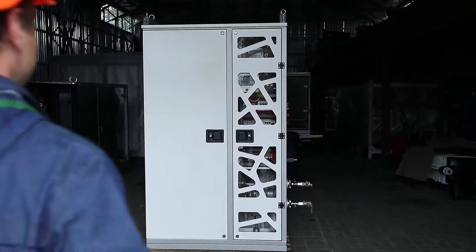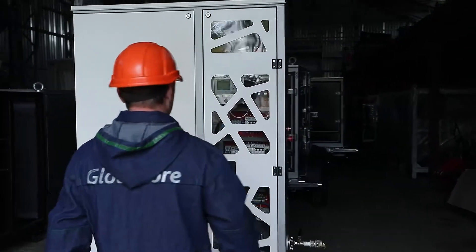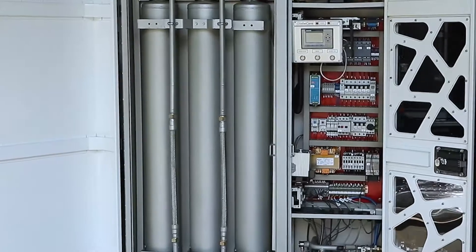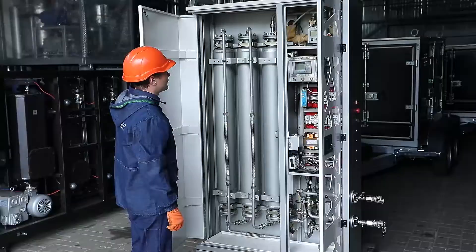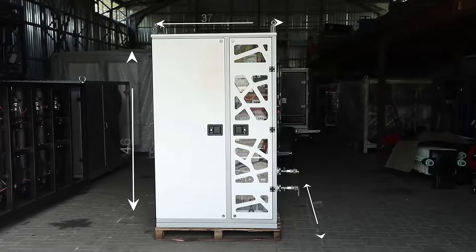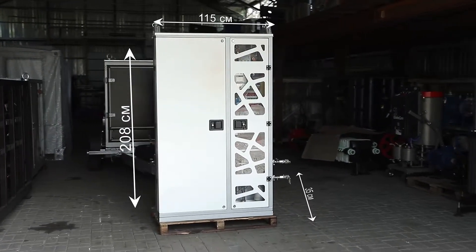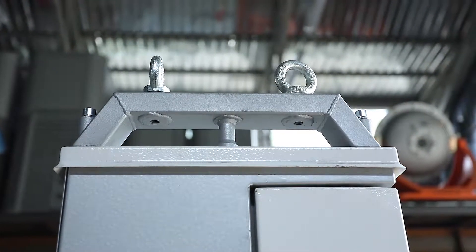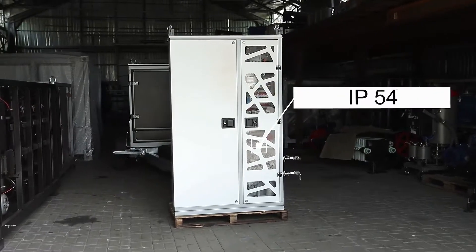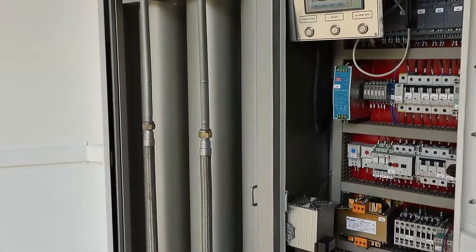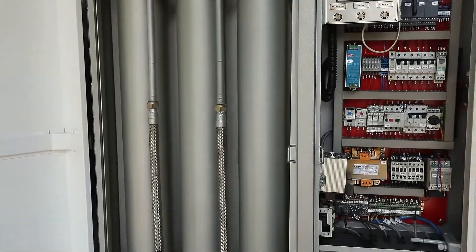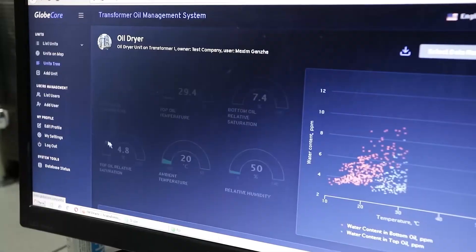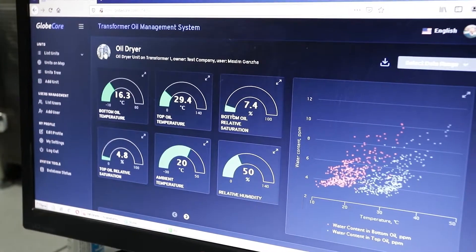Now about the advantages of the TOR system. It has a modern design and consists of the minimum required number of components: sensors, controllers, sorbent cartridges, pumps and valves. All components are housed in a sealed case 115 cm wide, 208 cm high and 35 cm deep. The housing rating is IP54. The sensors are reliably protected from damage and atmospheric precipitation, so the service life of the system is comparable to the service life of the transformer. Data visualization is user-friendly.